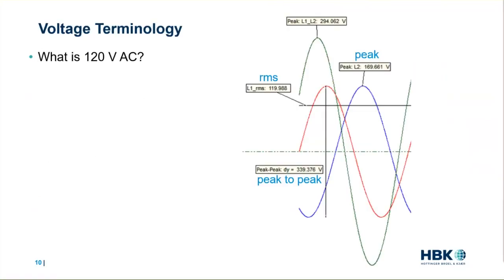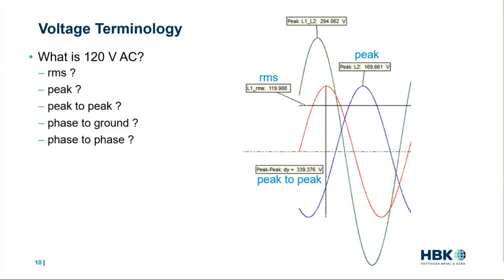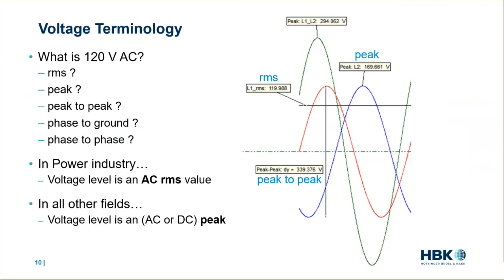So let's touch a bit on voltage terminology. Exactly what does it mean when somebody says, I want to measure 120 volts AC? Does that mean RMS, peak, peak to peak, phase to ground, phase to phase? You should always check and ask whenever someone states a voltage or a current in order to determine the actual amount of voltage or current involved. Now, the diagram on the right shows the relationship between RMS, peak, and peak to peak, such that 120 volts RMS is about 170 volts peak, which is about 340 volts peak to peak. Generally, in the power industry, voltage level is an AC RMS value, and in other fields, voltage level is an AC or DC peak. Again, don't assume, always ask.